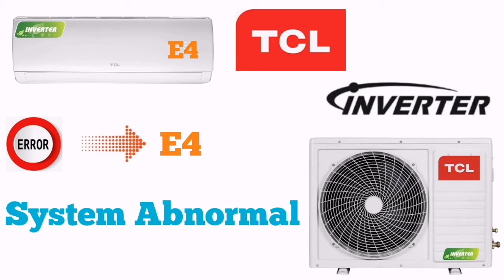it means there was the issue of the temperature sensor. And again, if it's getting the same problem, then you have to check if the refrigerant is getting blocked in the indoor or outdoor piping. Then you have to flush the piping and recharge the refrigerant. Start the system and your unit will be in working condition.